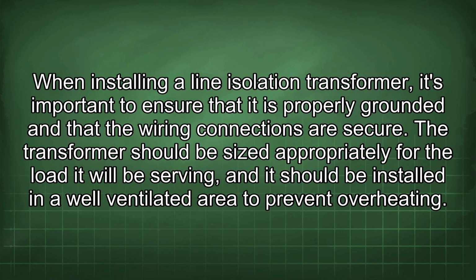When installing a line isolation transformer, it's important to ensure that it is properly grounded and that the wiring connections are secure. The transformer should be sized appropriately for the load it will be serving, and it should be installed in a well-ventilated area to prevent overheating.